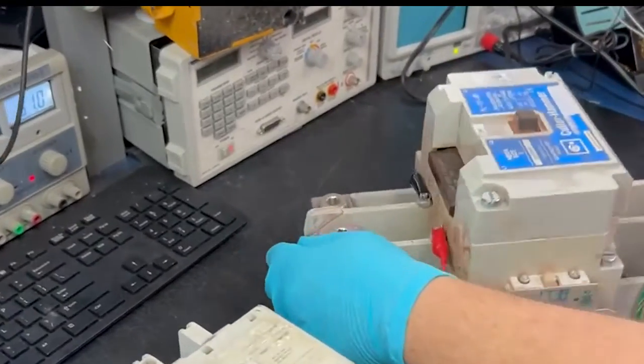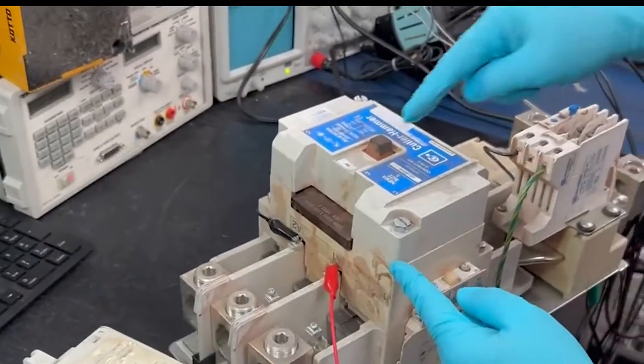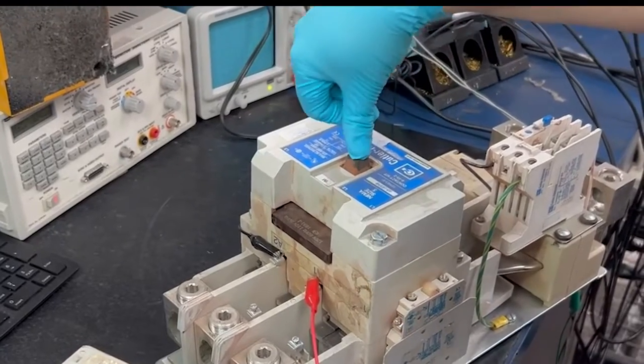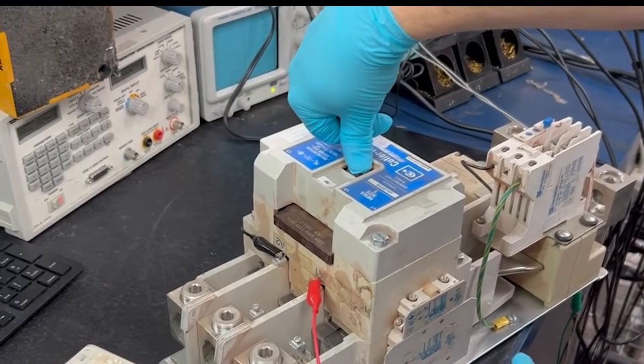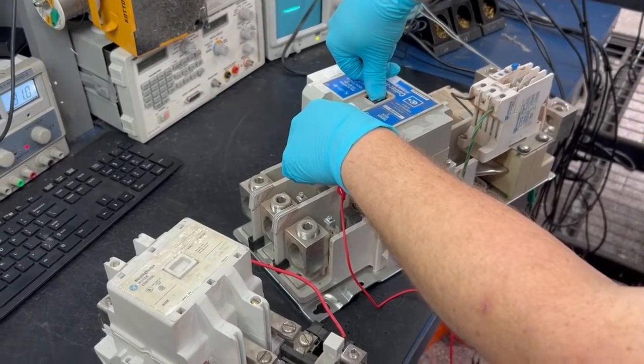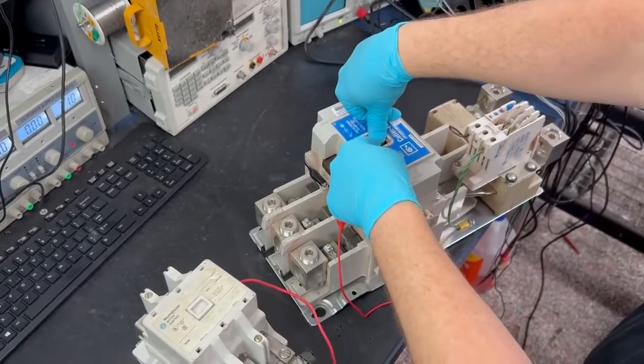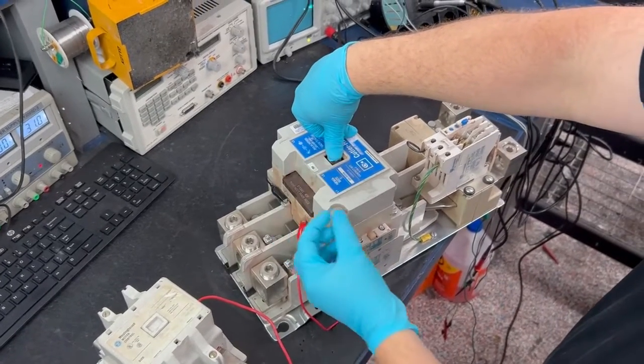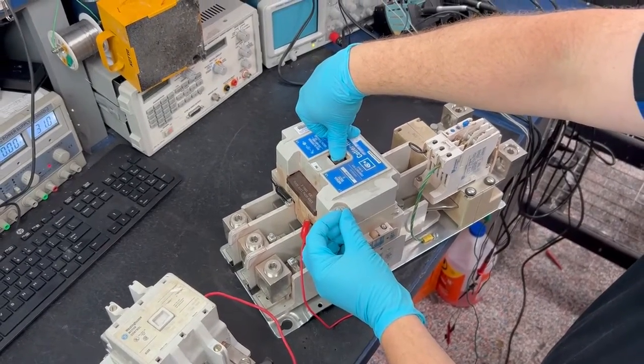What is happening here is that there is a coil which we will excitate in order to create a magnetic field that pulls in a set of irons to complete the circuit. However, the magnetism being generated is not strong enough to pull the contactor completely down. That's why there is noise occurring.